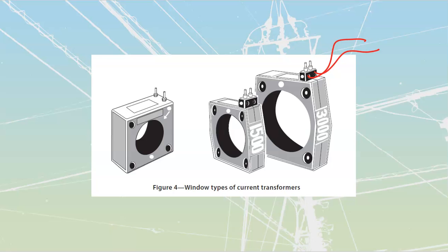When we install our metering inside that CT cabinet, we have to run our conductors through the window, and as we do, we're able to pick up its magnetic flux. The issue with these is that we're supposed to keep them centered - if they're off-center, we can have problems. If we grab the wrong lines and put them through there, we can have problems too. We need to have these things early on so we can pass our conductors through them.